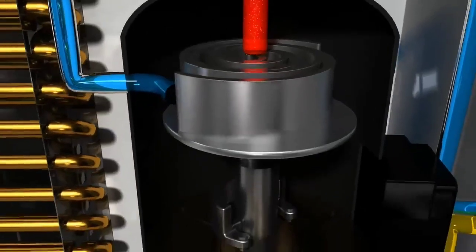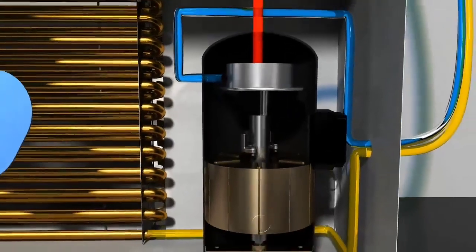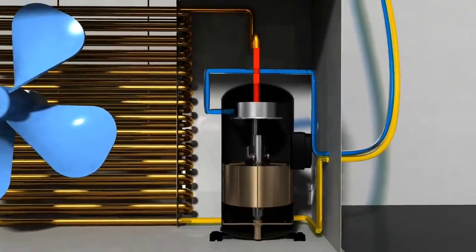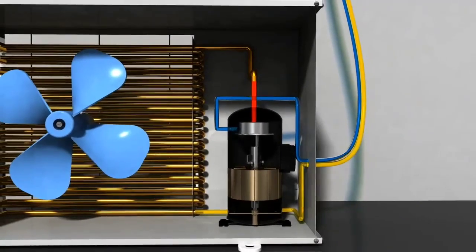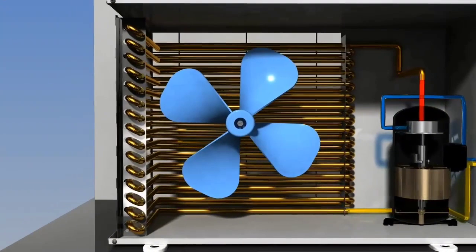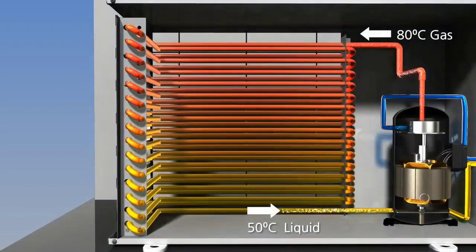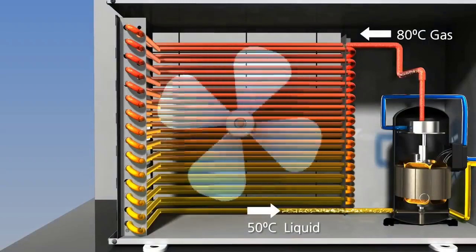The reason for using such type of a compressor is the efficiency of space utilization. This type of a compressor allows the machinery to become smaller in size and reduces noise as well as vibration. Compressed gas is then sent to a condenser to be pressed into liquid. The temperature of refrigerant passed through the compressor is above 80 Celsius, which is in a hot gas state.